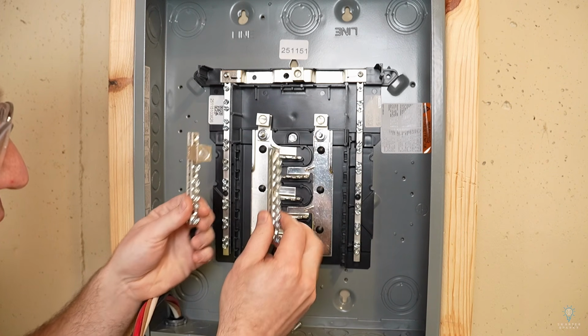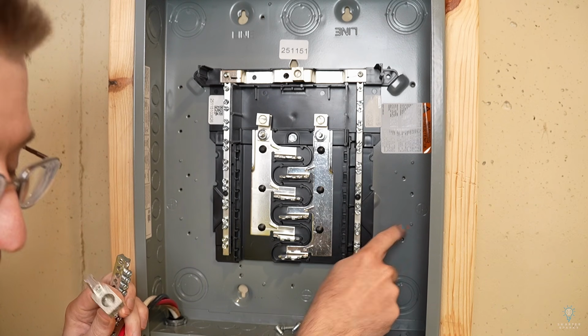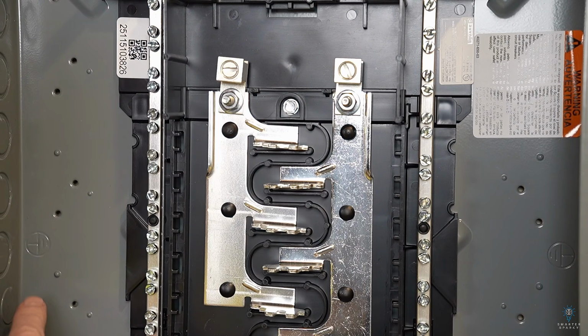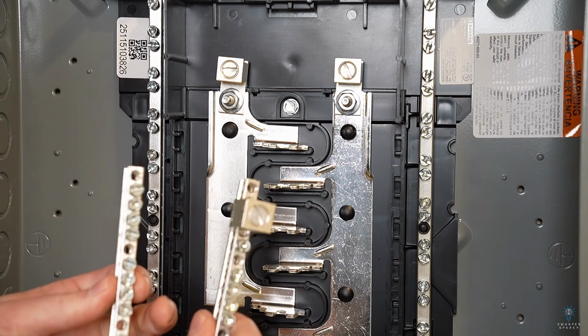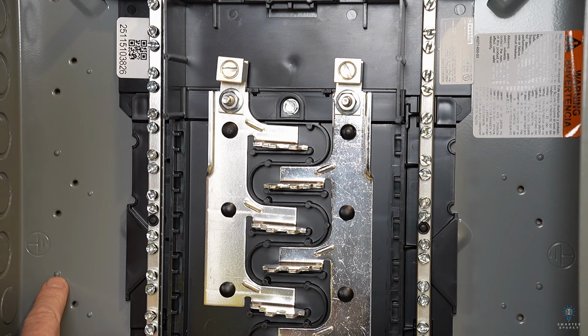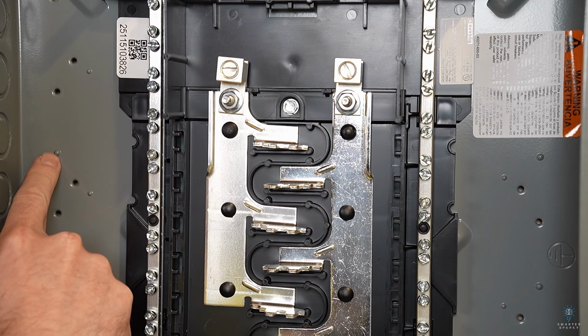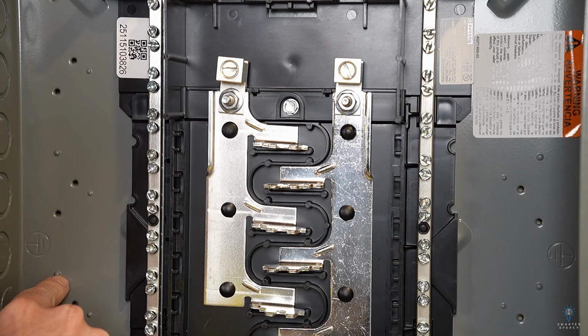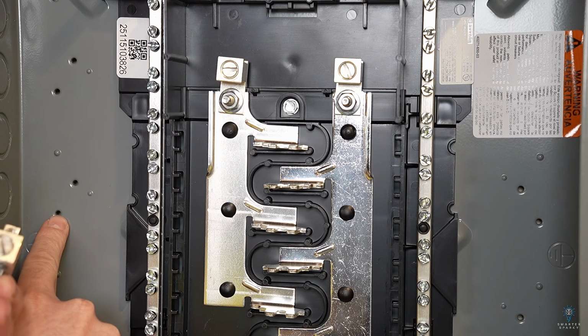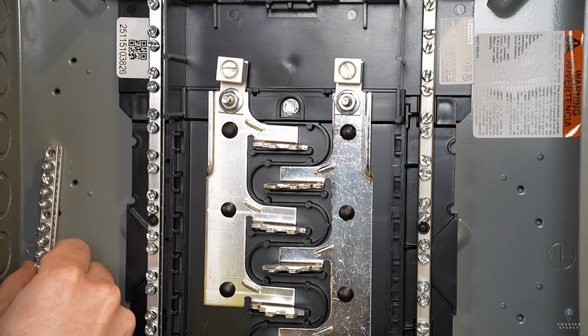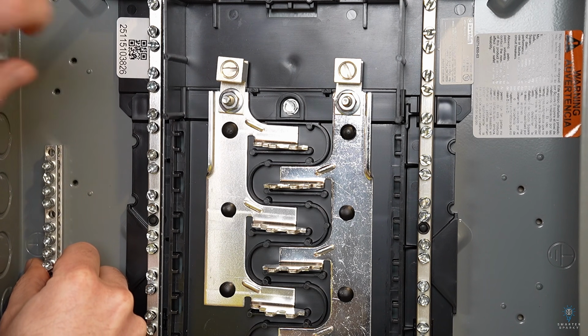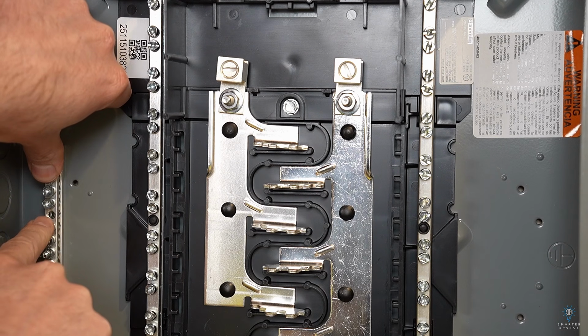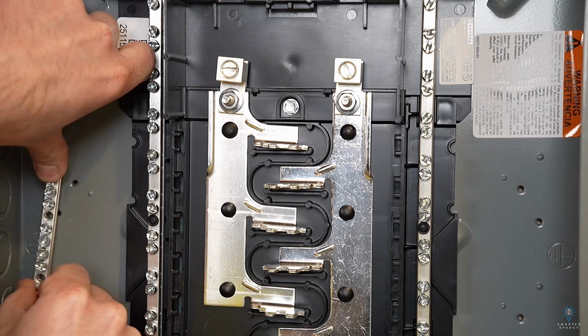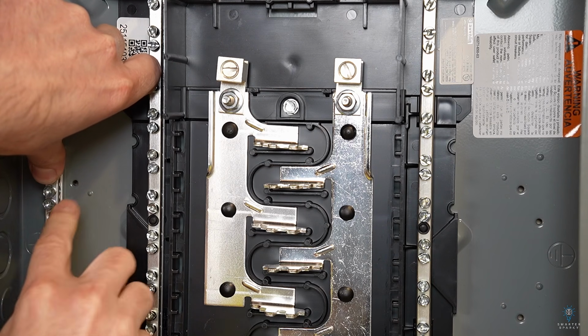So these two ground bars are actually going to be installed directly into the panel. And if we zoom in here, we can see that there are two ground symbols right on the panel. Now, there's actually 4 different places we could install these ground bars. Notice this little nub right here. We could use that little nub, and there's another nub right here. So that would put a nub on the top and a nub on the bottom. And then right in the middle, we could run a screw. So if we wanted, we could install our ground bar right here and only need to put one screw in the middle, and then those nubs will prevent the bar from rotating side to side.